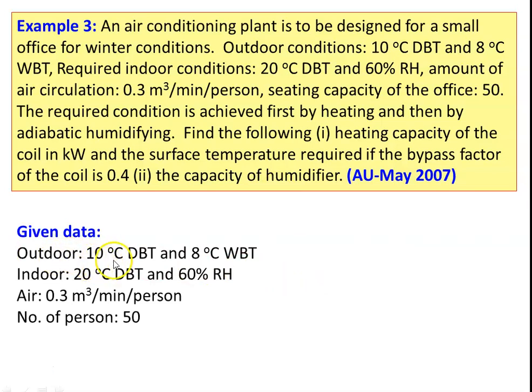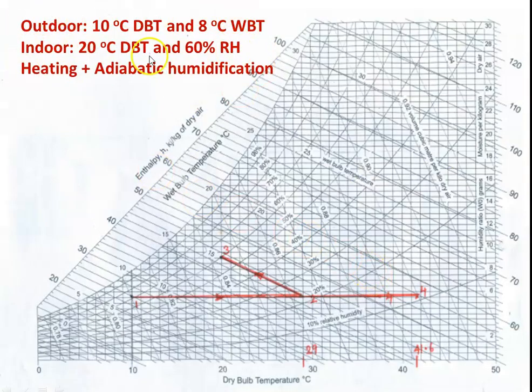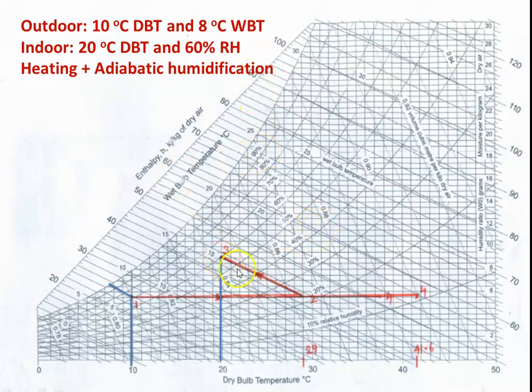Write down the given data. Outdoor condition: 10°C dry bulb, 8°C wet bulb. Indoor condition: 20°C dry bulb, 60% relative humidity. Air quantity: 0.3 m³/min per person, 50 persons. On the psychrometric chart, locate the initial (outdoor) and final (indoor) points. The process is achieved by heating then adiabatic humidification. For adiabatic humidification, enthalpy is constant.